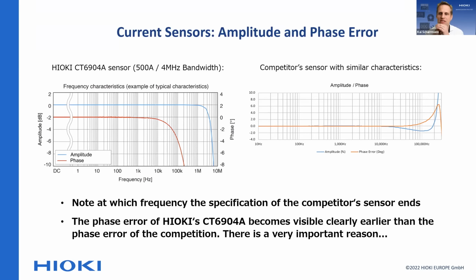Just have a look at the frequency end of our specification versus the competitor's. The competition stopped specifying amplitude and phase error already at 300 kilohertz, which is the third harmonic if your base frequency, like in SiC, is 100 kilohertz. Our sensor, on the other hand, goes far into the megahertz range in terms of specified bandwidth.